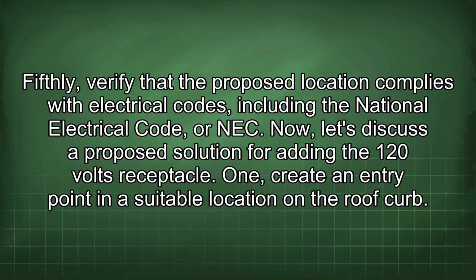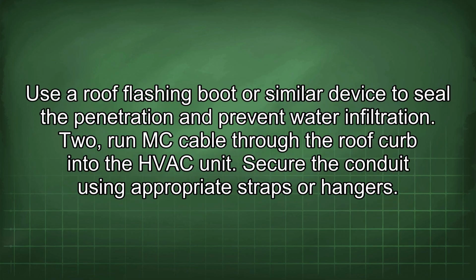Now, let's discuss a proposed solution for adding the 120-volt receptacle. 1. Create an entry point in a suitable location on the roof curb. Use a roof flashing boot or similar device to seal the penetration and prevent water infiltration. 2. Run MC cable through the roof curb into the HVAC unit. Secure the conduit using appropriate straps or hangers.